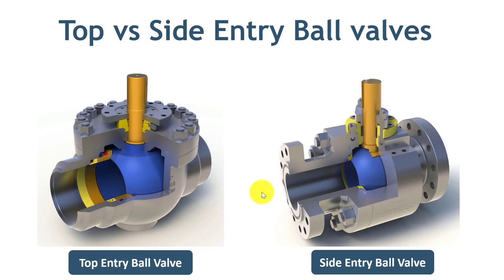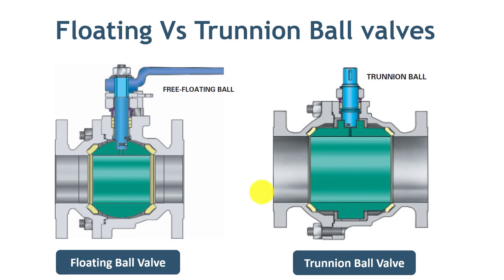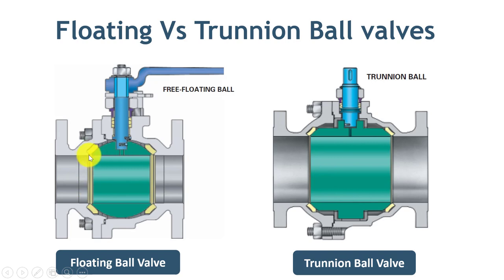Can you see the difference between the two types of ball valves shown here? The first one is a floating type ball valve and the second is a trunnion-mounted ball valve. In a floating ball valve, the disc is floating with the fluid — meaning when there is pressure on the upstream of the valve, it will push the ball toward the downstream seat, so your pressure helps achieve better shutoff. The negative side is that you need high operating torque in high-pressure service to operate the valve.